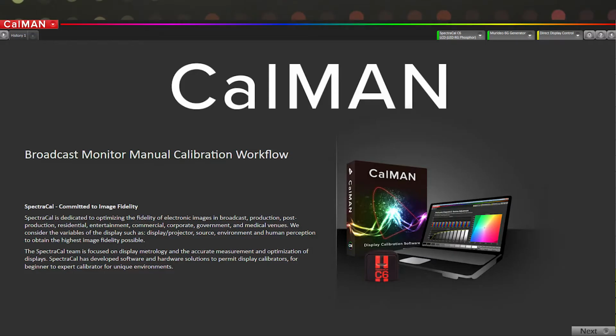The next thing that we added is something called a broadcast monitor workflow. This is in CalMan Ultimate and CalMan Studio. A lot of people in the studio market have a lot of broadcast monitors or reference monitors that you have to manually calibrate with the menus, but they really only have a 2-point white balance control and stuff like that. So they wanted a simplified workflow specifically targeted towards broadcast monitors, so they didn't have to skip any steps that don't apply to them. So we created a broadcast monitor workflow just to simplify their calibration processes. That's in CalMan Studio and CalMan Ultimate.